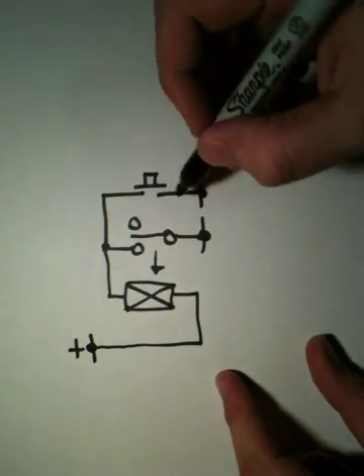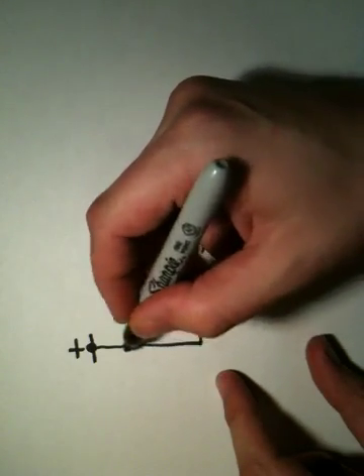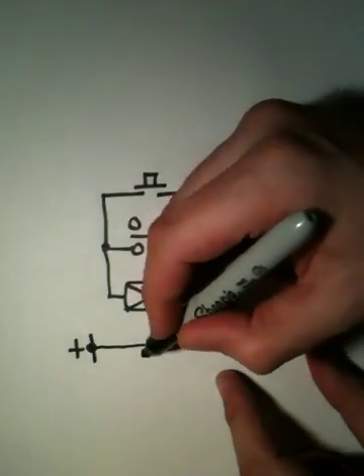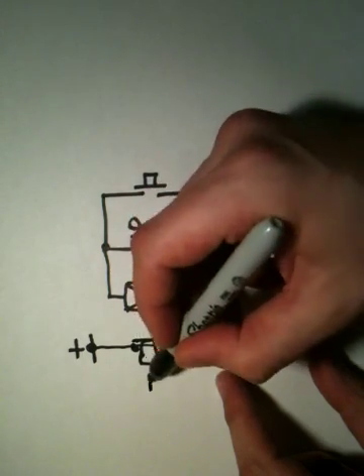If we want to have the relay turn off as well with another push button, then we need to break this connection here. The way we do that is we have another push button in here, but it's actually a push button that opens when you press it.